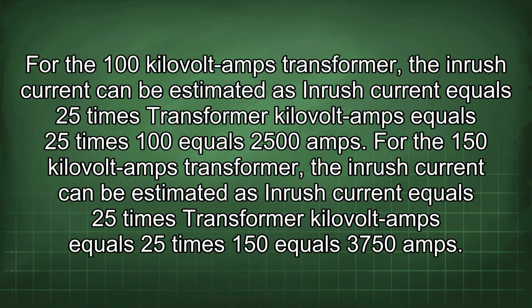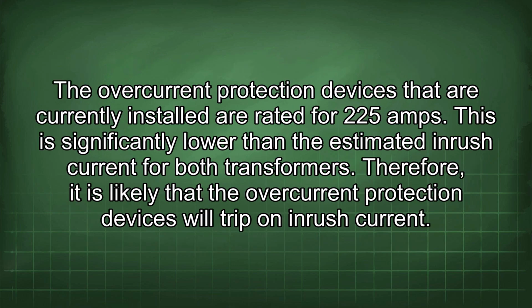For the 100 kVA transformer, the inrush current can be estimated as inrush current equals 25 times transformer kilovolt-amps equals 25 times 100 equals 2500 amps. For the 150 kVA transformer, the inrush current can be estimated as inrush current equals 25 times transformer kilovolt-amps equals 25 times 150 equals 3750 amps. The overcurrent protection devices that are currently installed are rated for 225 amps.